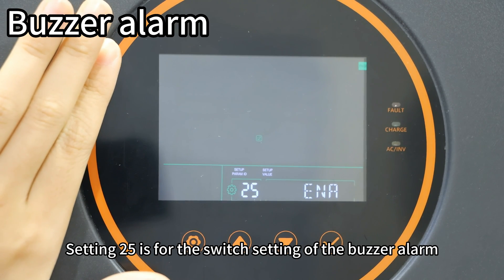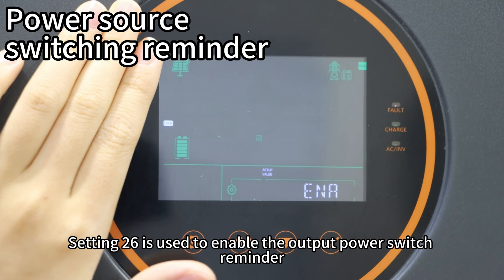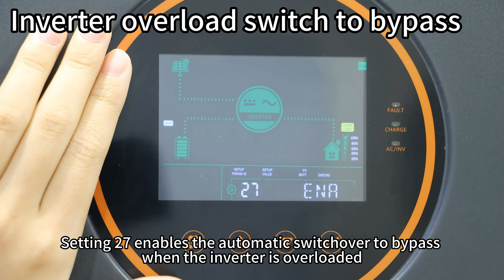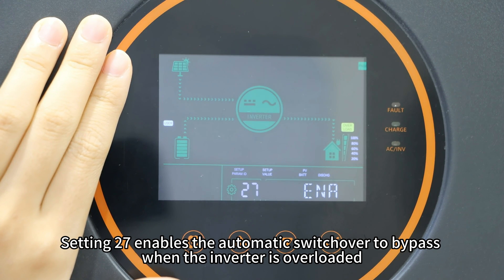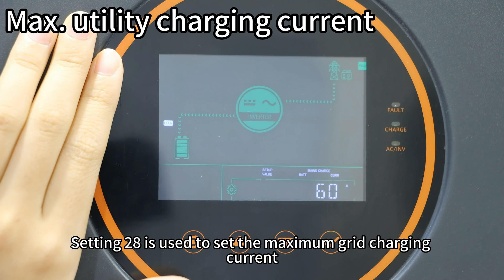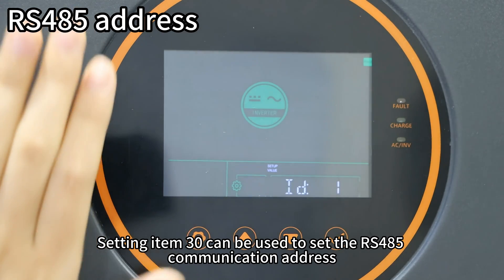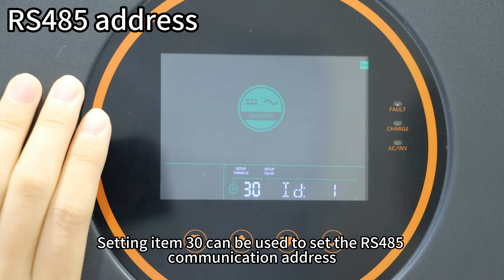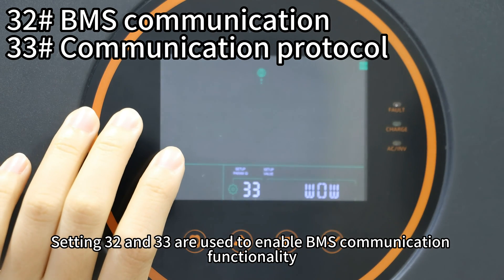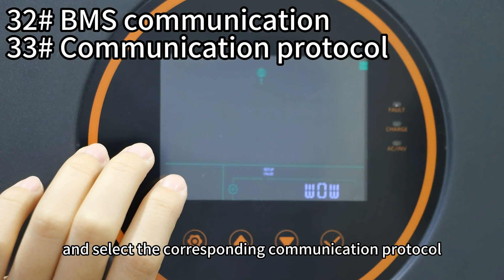Setting item 25 is for the switch setting of the buzzer alarm. Setting item 26 is used to enable the output power switch reminder. Setting item 27 enables automatic switchover to bypass when the inverter is overloaded. Setting item 28 is used to set the maximum grid charging current with a maximum value of 120A. Setting item 30 can be used to set the RS485 communication address. Setting items 32 and 33 are used to enable BMS communication functionality and select the corresponding communication protocol.